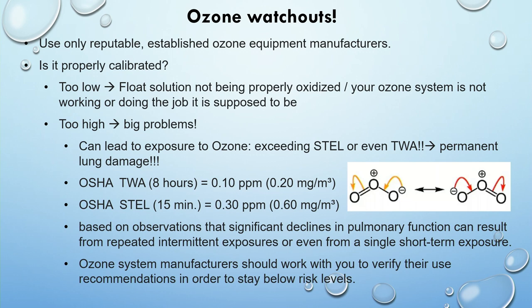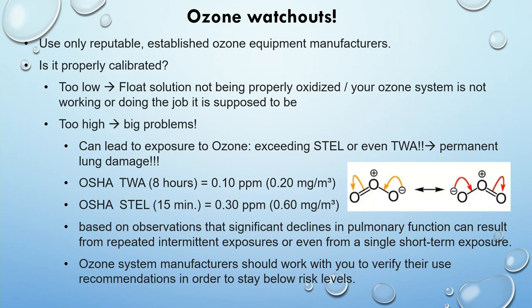For ozone, there are different watchouts. Only use ozone systems from reputable, well-established manufacturers. Is your ozone system properly calibrated? If it's too low, you'll have insufficient oxidation and that's going to affect disinfection. If it's too high, you could have an exposure to ozone. If that exposure were to exceed what's called the short-time exposure limit or the time-weighted average — those are two different values with two different meanings — you could suffer permanent lung damage. If you have any concerns, reach out to your ozone system equipment manufacturer to review their use recommendations and ensure you're staying below these risk levels.